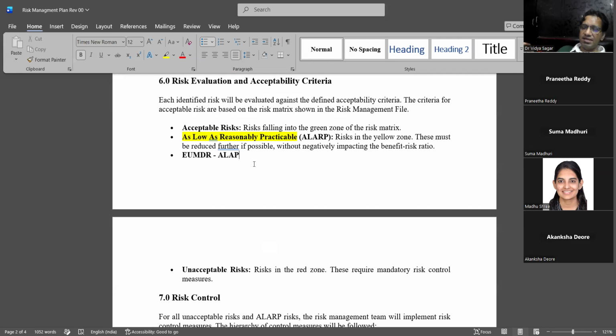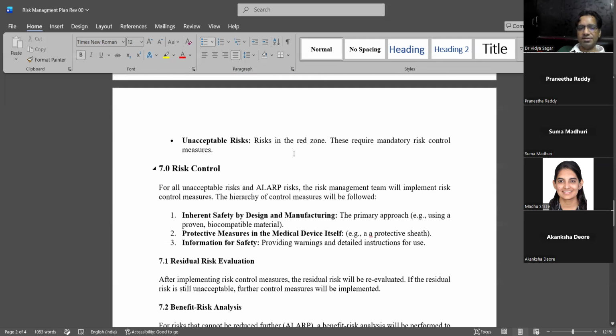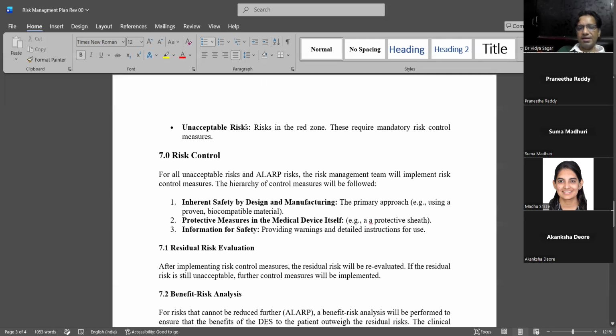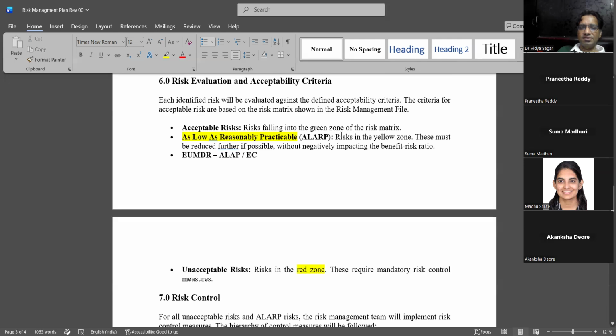If you want to spend money, redesign, redo all the design and development, you do it. Spend money on it. If it is $10 million, spend it. That is what we call economic considerations. Without economic considerations, you spend money on your device and bring the risk as low as possible. That is what EU MDR says, whereas ISO 14971 includes economic considerations. And there are a few other things where EU MDR has contradictions, I'll tell you in the lecture notes. There will be unacceptable risks, which we generally call risks in the red zone. If the risks are acceptable, generally they will be in the green zone.